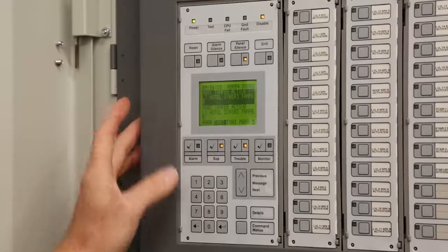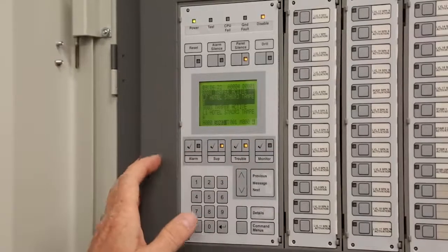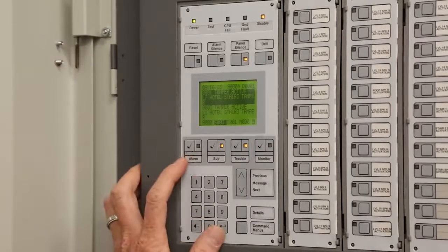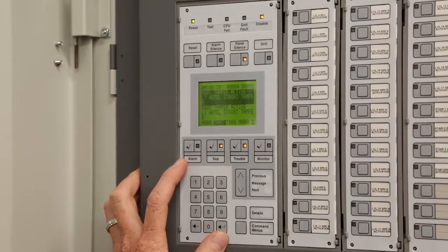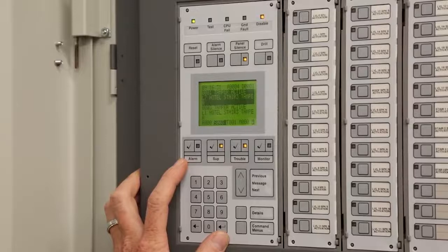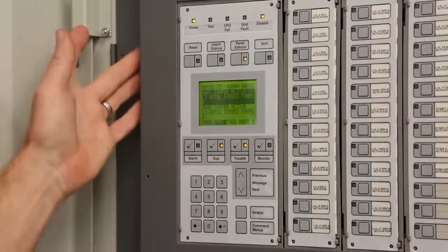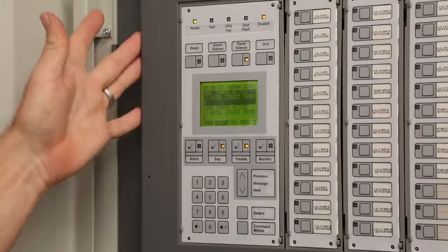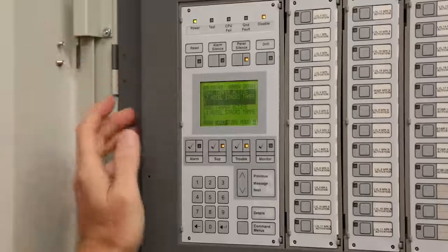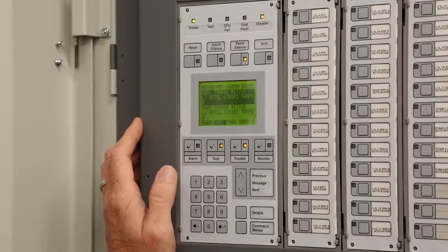Basically, on the main panel here, it has indicator lights below it. Red would be alarm. Alarm conditions would be pull stations, heats, smokes, Ansul system, or flow switches. So alarms would basically have your message notification go out, and your strobes will be going off. It will shut down associated air handlers in that area and all that.